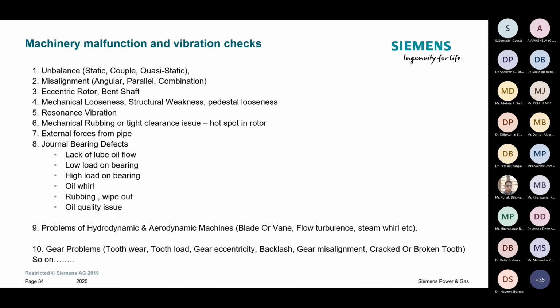External force from the pipe, yes, there are piping structures connected with the steam turbine. They also try to expand thermally, and when they expand, they try to push or pull the rotating and stationary body. While doing that, your alignment will be disturbed between rotating and stationary components. Then these rotors are supported on journal bearings. So the journal bearing has its own complexity.